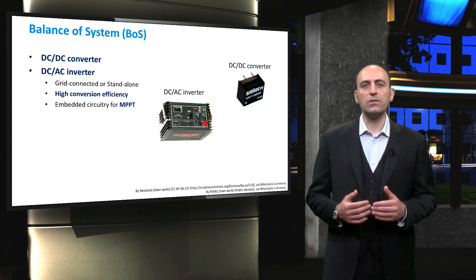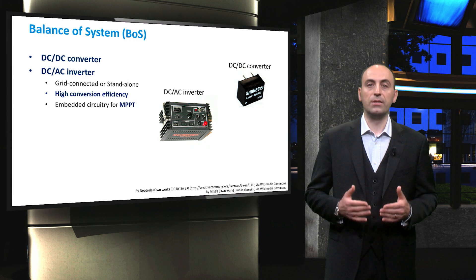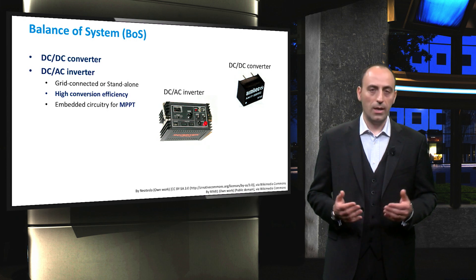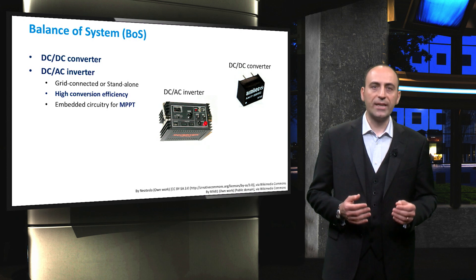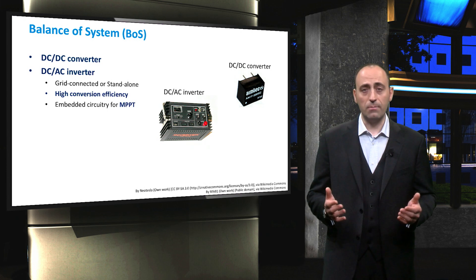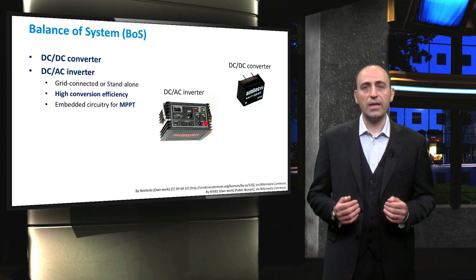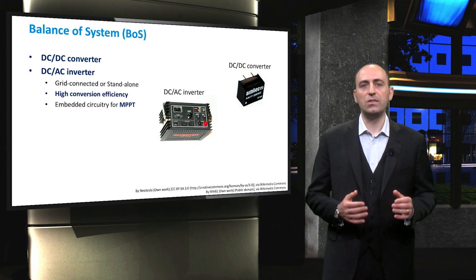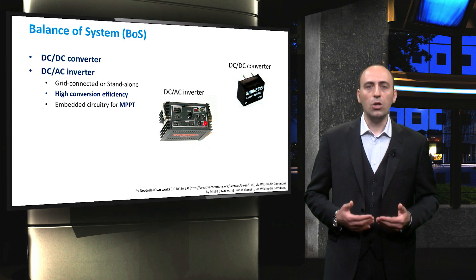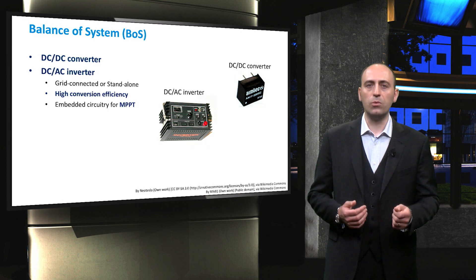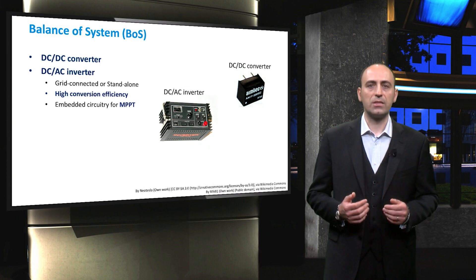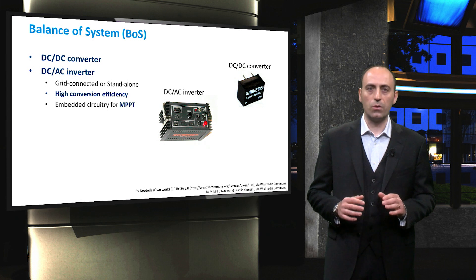Furthermore, inverters can contain an additional board in the circuitry for actuating a maximum power point tracking strategy. As a result, the PV module can operate at the maximum power point voltage. In fact, many inverters have an embedded DC-DC converter to change the variable voltage of the PV array to a constant voltage that is the input for the actual DC-to-AC converter. We will discuss maximum power point tracking in more detail later in this course.